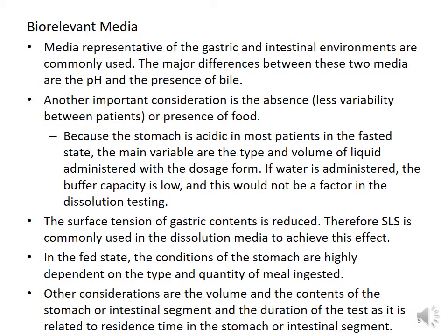If water is the administered fluid, the buffer capacity is low, and this would not be a factor in dissolution testing. Although it is known that the surface tension of gastric contents is reduced, the exact physiologic agents that are responsible are not known. Therefore, sodium lauryl sulfate is commonly used in dissolution testing to achieve this effect.